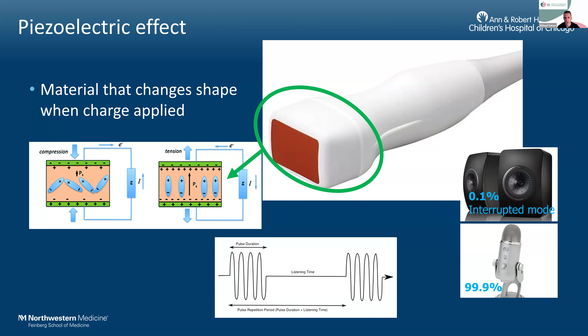And then conversely, these crystals can also generate charge when pressure waves are applied to them. So in typical operating mode, ultrasound probes spend only a minority of time actively making sound, and most of the time actually listening. It's about 99.9% of the time. And plotted as pressure versus time, you can see that ultrasound probes generate pulses, which come in bursts. The time between these bursts is called pulse repetition period, which will become important later on in this discussion.